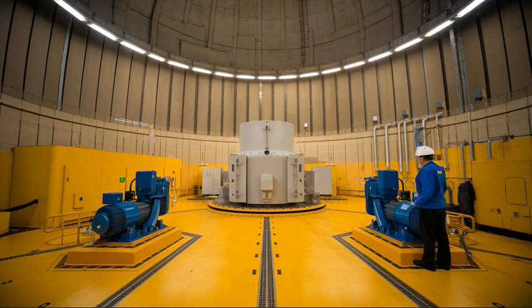Range and selection. In a typical gigawatt nuclear power plant, between 400 and 800 LV motors are installed to support various critical and auxiliary systems. The exact number can vary depending on the plant design, the type of nuclear reactor, for example, pressurized water reactor (PWR), European pressurized reactor (EPR), or others, and specific operational requirements. The voltage of the LV motors is from 380 to 690 volts AC. The common voltage of those is 460 or 480 volts in USA NPPs or 400 or 415 volts in European NPPs.